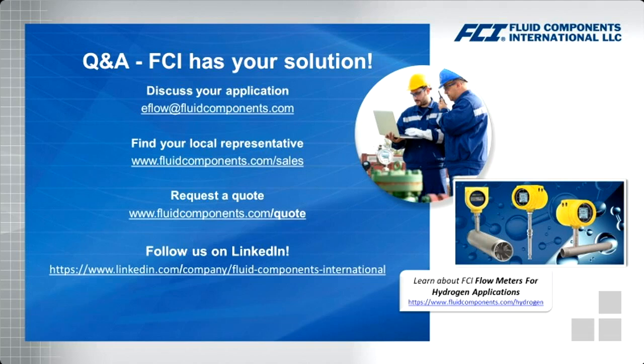What kind of questions do I need to ask a manufacturer to make sure my meter is accurately calibrated for hydrogen? Boy, that's another great question. There's a lot that's involved with that. First of all, upon the initial issuance of a quotation for an application, you need to ask what tool they used to do the calculations to make sure that the meter's properly applied for the application. And then beyond that, ask a little bit about their calibration process. Are they using traceability standards in their Cal Lab, such as NIST? Ask about what ranges and flow rates they're able to test at, and be sure you have the full understanding. And then once that meter is calibrated, are they supplying certified calibration documentation along with it? Those are really the key points to be concerned about.